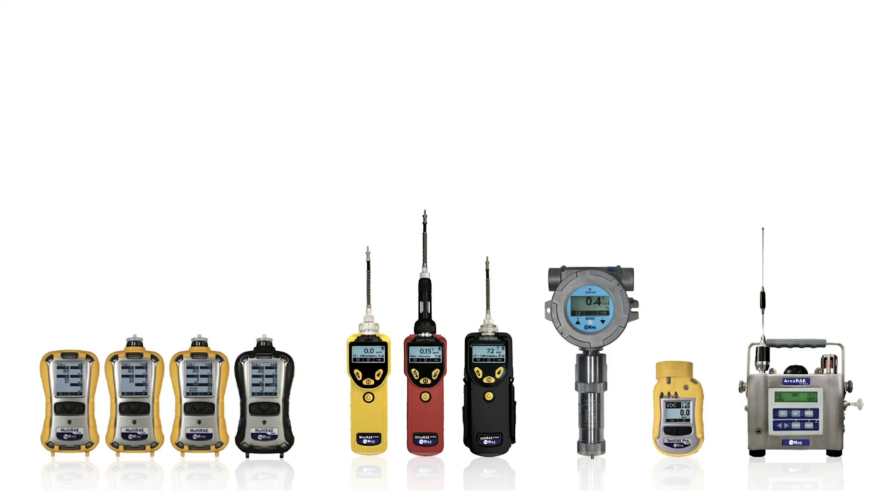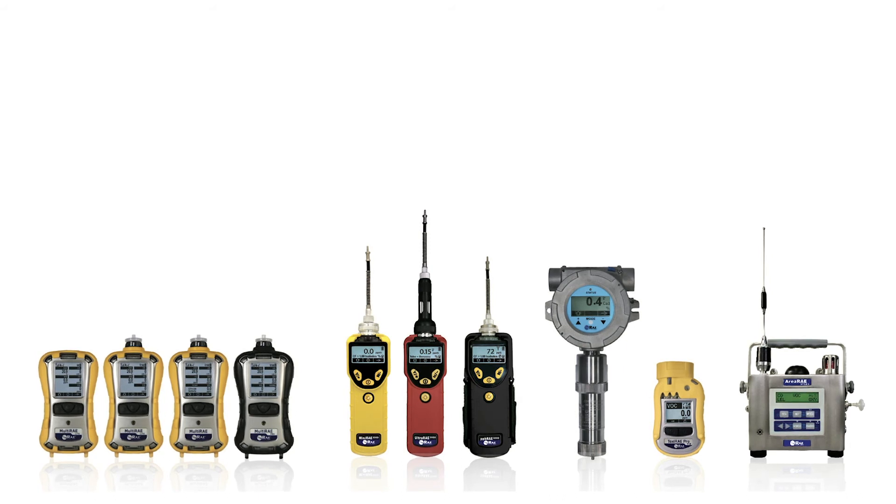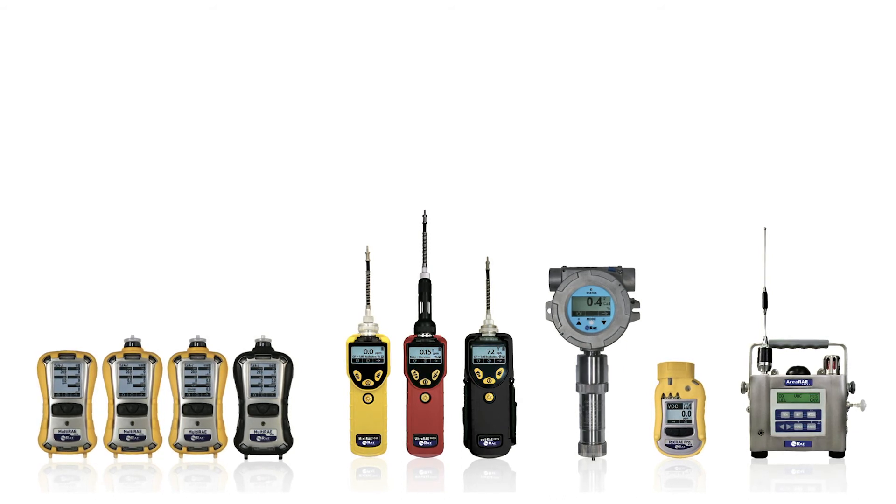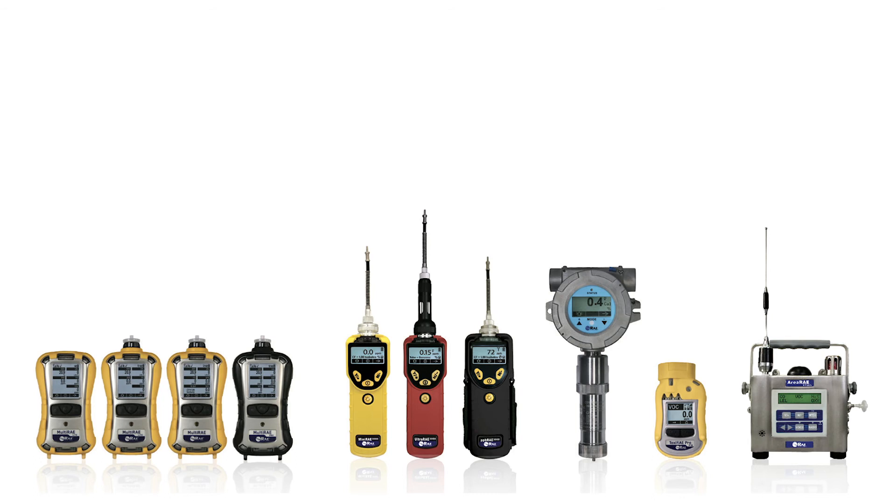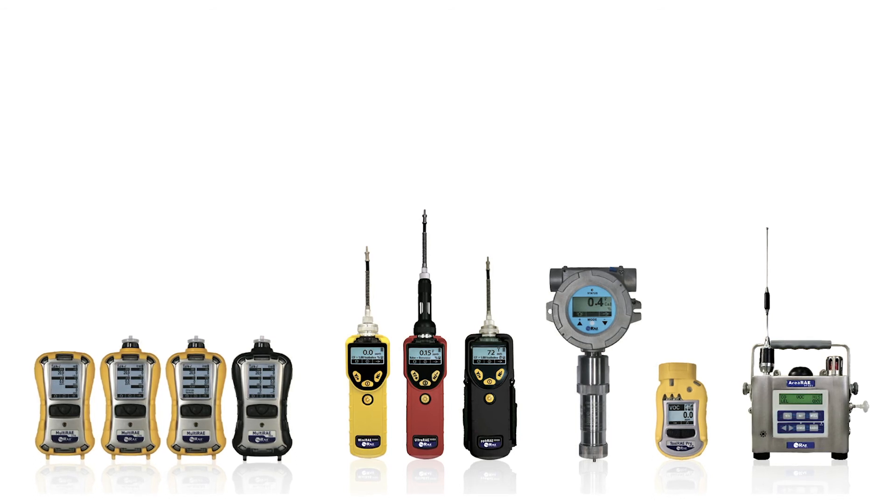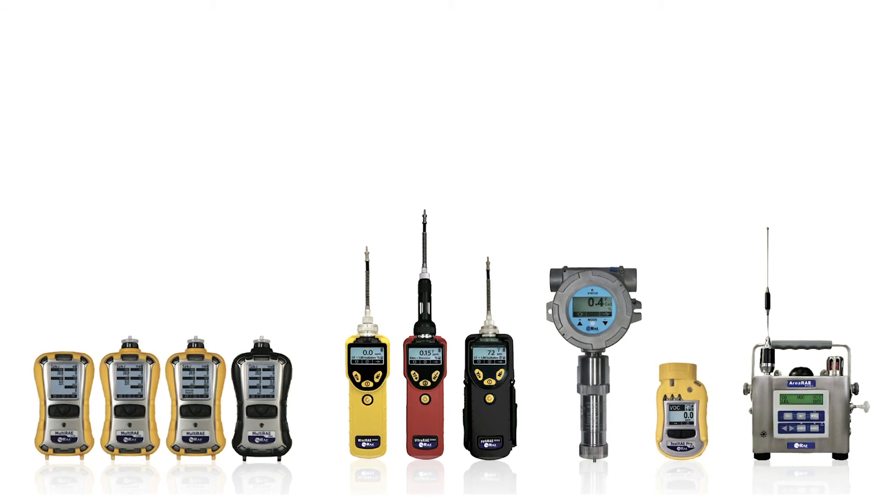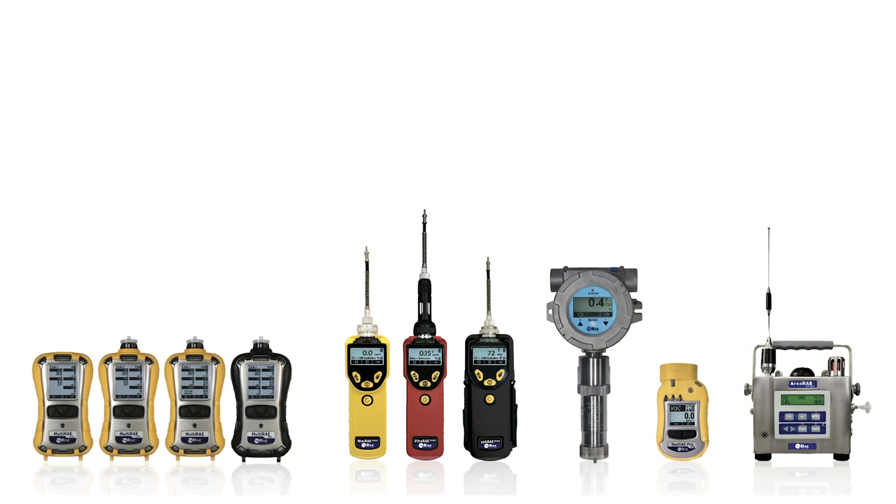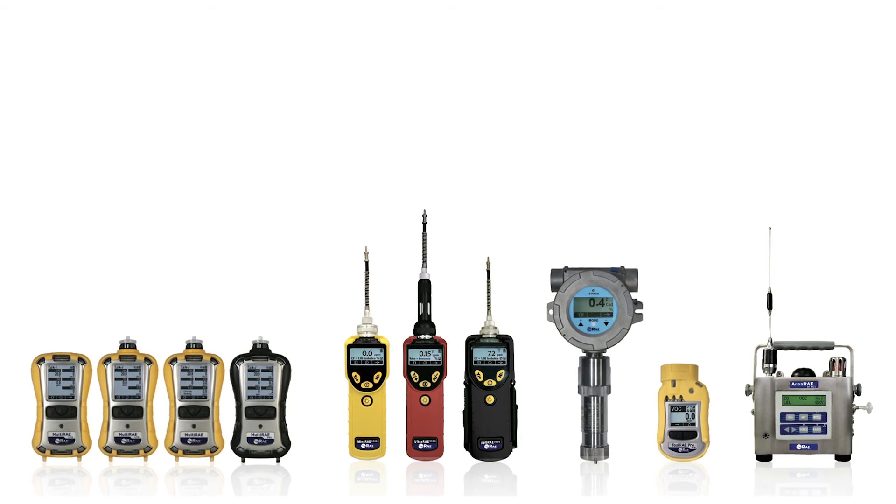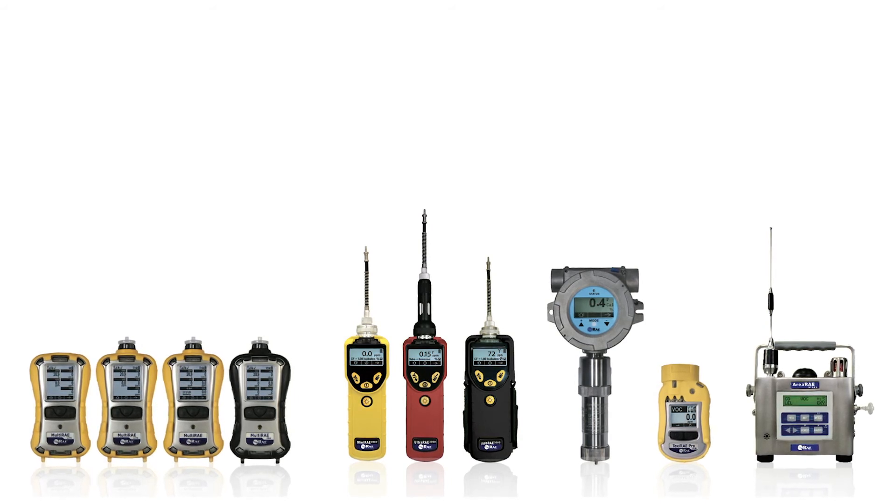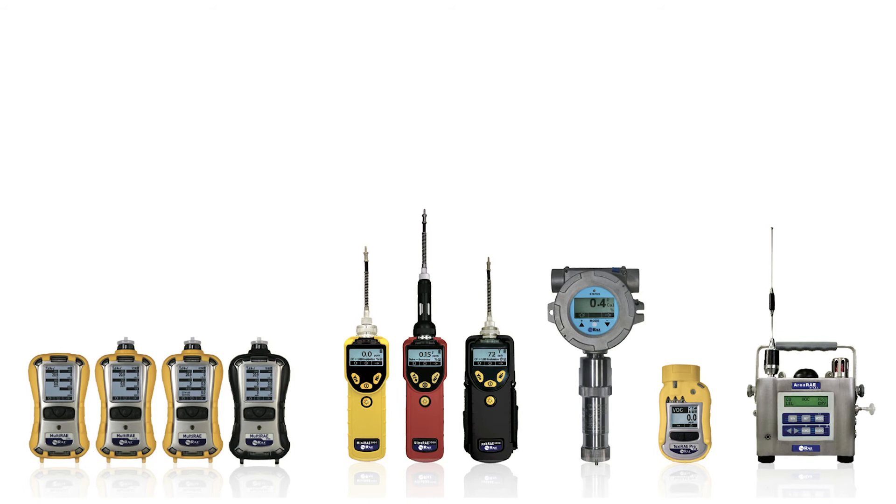Now that we know what a correction factor is, let's see how to apply correction factor in your reading. A practical example with the monitor in hand and walking through the correction menus. Most instruments allow you to apply the correction factor by selecting the gas from the library in the memory, so no math has to be done to this reading.